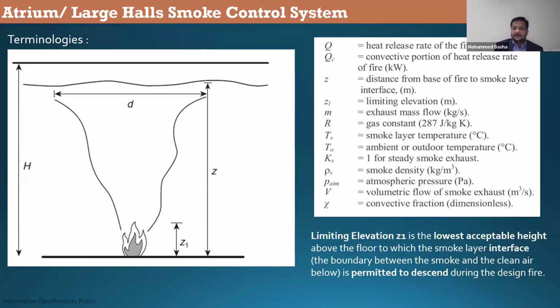Z, I explained to you, is the distance from the base of the fire to the smoke layer. Z1 is the limiting elevation. M is the exhaust mass flow. R is the gas constant. T is the smoke layer temperature. T0 is the ambient or outdoor temperature. Then the next are constants: smoke density, atmospheric pressure, volumetric flow of smoke exhaust, convective fractions. We will discuss more when we go into the next slides.